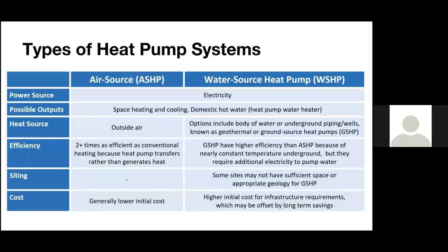The water source or ground source heat pumps tend to work with water that doesn't get as cold as the outdoor ambient. So we normally design the water loops to not get much colder than around 50 degrees Fahrenheit in a typical geothermal project. So the water source heat pump never really has to go extract heat from air at 0 degrees. It does so from water at 50. So that's why ground source or water source heat pumps will be more efficient, but then you're not done there. You have to move the water around as well. So you really have to look at the entire energy use of a building when comparing the two.